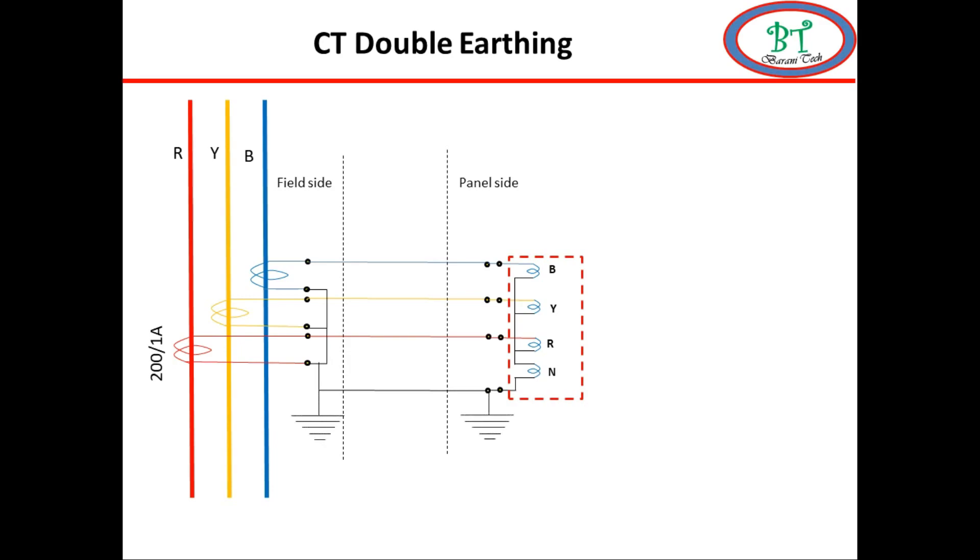During normal running condition the current on three phases balance. Let us consider 100 amps on each phase. According to CT ratio the secondary side will produce 0.5 amps. And the neutral side current will be 0. We are considering the earth fault production is taken from the neutral side current.